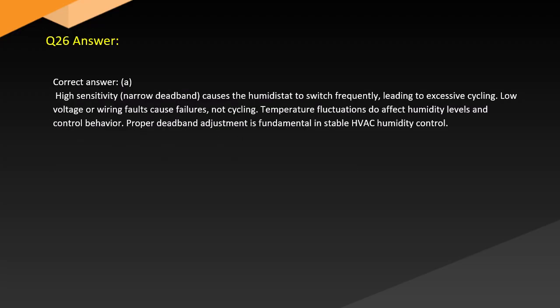Answer. Correct answer. A. High sensitivity, narrow deadband causes the humidistat to switch frequently, leading to excessive cycling. Low voltage or wiring faults cause failures, not cycling. Temperature fluctuations do affect humidity levels and control behavior. Proper deadband adjustment is fundamental in stable HVAC humidity control.